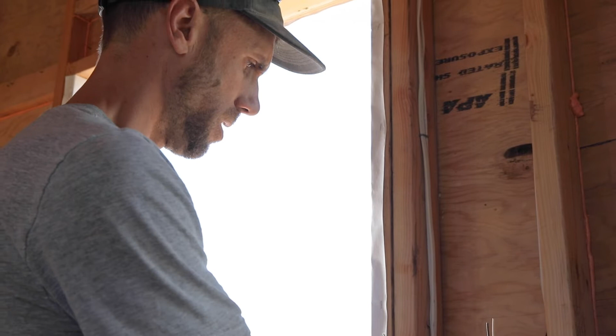Once again, we'll tie all of our neutrals together. One thing to keep in mind is we're only allowed to tie these together because they're all on the same circuit breaker. Sometimes a box has wires from 2 different circuit breakers, and in that case you need to keep those neutral wires separate. But all of these are part of our lighting circuit, so they're all on the same breaker, and we can tie all the neutrals together.